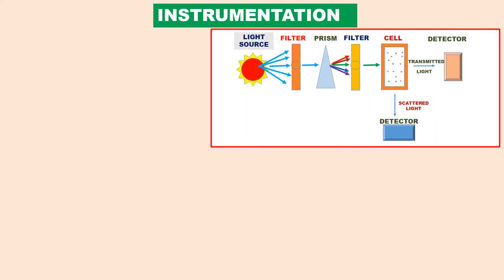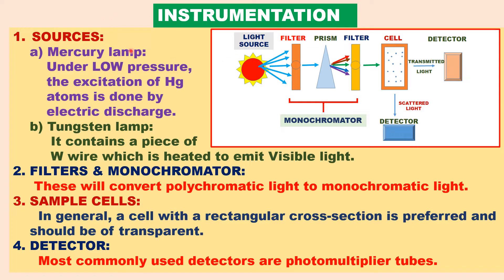The components present in the instrument for nephelometry and turbidimetry are as follows. The light source is very important; mercury lamps or tungsten lamps are used. Under low pressure, the mercury lamp excites mercury atoms by electric discharge to emit light. The tungsten lamp contains a piece of tungsten wire which is heated to emit visible light. Filters and prism convert light to monochromatic light. Sample cells with a rectangular cross-section are preferred and should be transparent. Photomultiplier tubes are mostly used as detectors for nephelometry and turbidimetry.